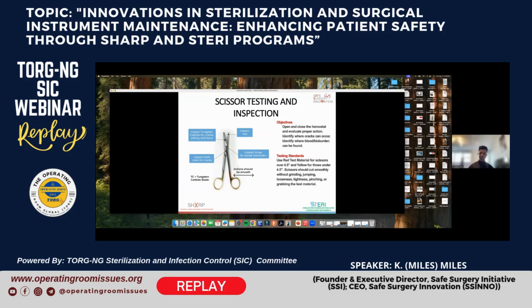So having that knowledge will empower OR professionals to say, hey, this is unsafe, and these are the reasons why. And when you have that, then you can go to your administrator and say, these are the reasons why it's broken, these are the reasons why things need to be replaced, and we need to get an order or find a new piece of equipment. So that being said, if you don't have the ability to test and inspect instruments, then there's no way to do that quality control before it makes it to the patient.